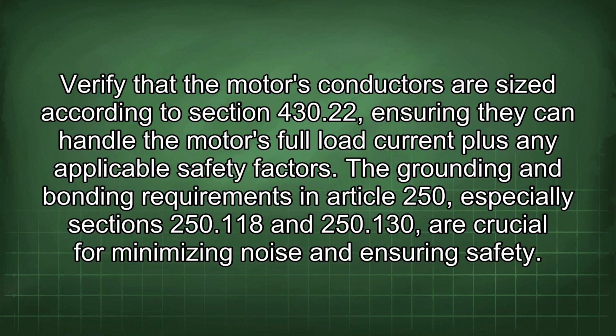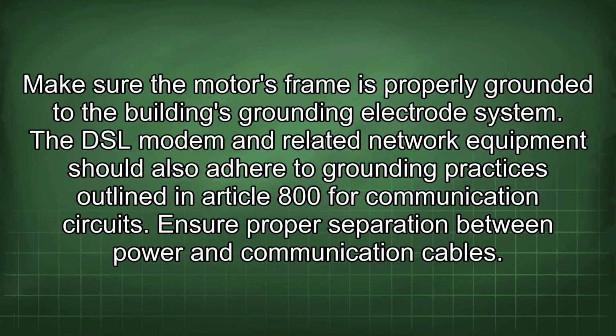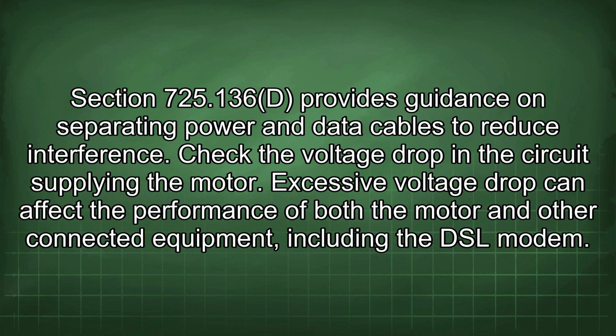The grounding and bonding requirements in Article 250, especially sections 250.118 and 250.130, are crucial for minimizing noise and ensuring safety. Make sure the motor's frame is properly grounded to the building's grounding electrode system. The DSL modem and related network equipment should also adhere to grounding practices outlined in Article 800 for communication circuits. Ensure proper separation between power and communication cables. Section 725.136(D) provides guidance on separating power and data cables to reduce interference.